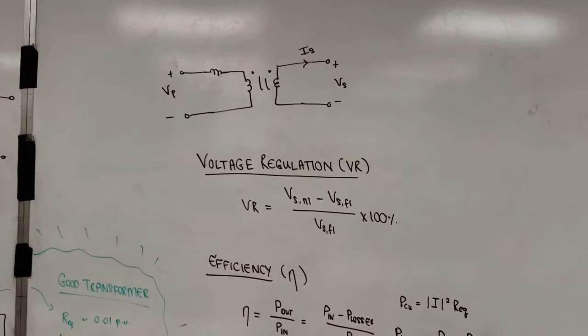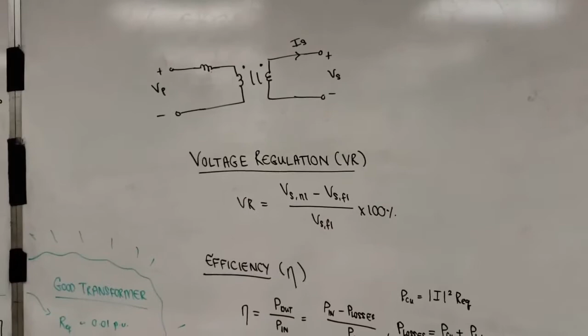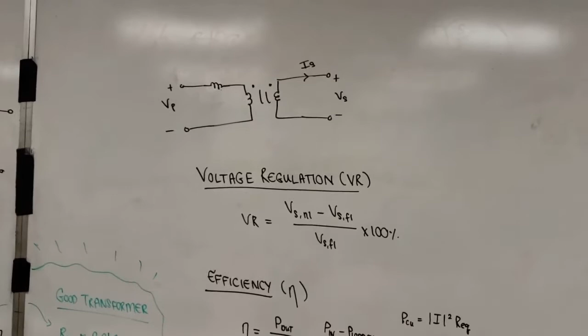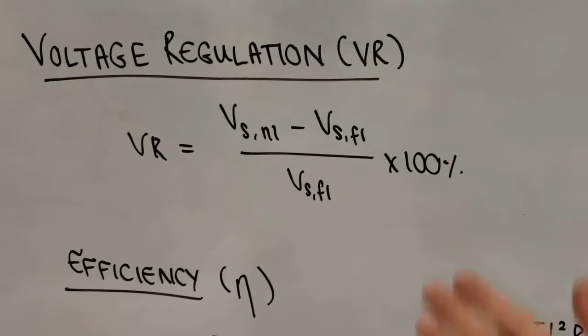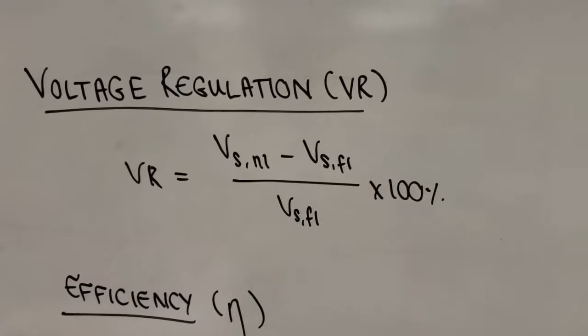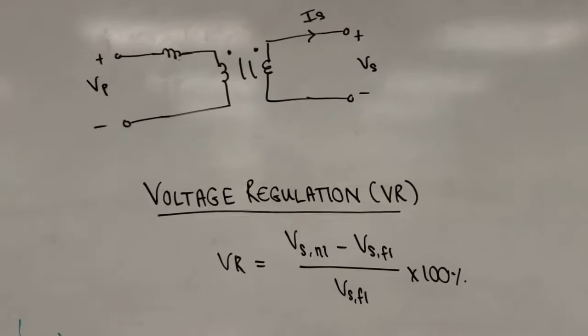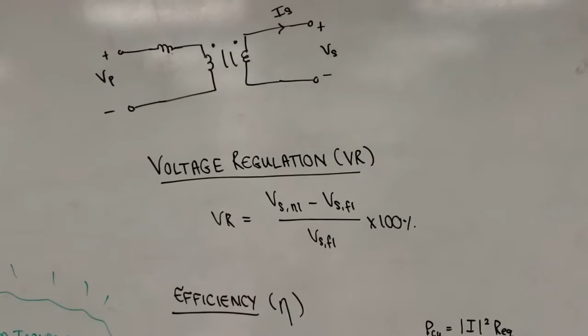If you can describe the transformer impedances, these parameters, in terms of per unit, then we have a nice range of values that we can say are good, to characterize a good transformer. For example, if you referred all the impedances to one side so that you have an R equivalent and an X equivalent - here I referred it to the primary side - remember, if you're referring anything from secondary to primary, you're multiplying by the turns ratio. So that R equivalent, I wrote down, is the primary resistance plus the secondary resistance multiplied by the turns ratio squared. I put approximately because there are the parallel branches there too, so we're kind of referring across those as well. In any case, just remember how to refer impedances back and forth - refer everything to one side.